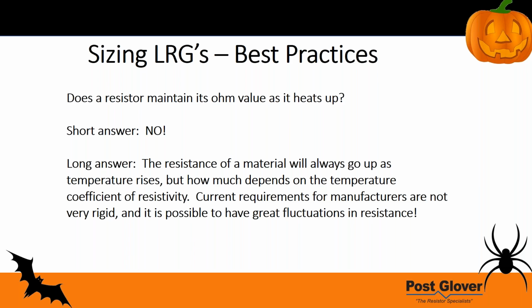That can impact your relay settings, and it could potentially be an issue. So I'd posit that if you want a tighter requirement - say you're the system design engineer and you want these to be 100 amp resistors, and you'll worry about relay coordination yourself - the tighter you set that, the more you need to worry about this consideration.